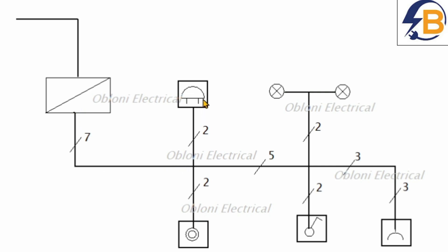Adding the two feed wires to the three socket cables, we now have five cables already. This is very important: because we are using different feeds for the bell and the switch, these two circuits must be on their own — a separate circuit for the bell and a separate circuit for the light. If we have a separate feed, there must be a separate neutral to the bell and a separate neutral to the light. Two neutral wires added to the five gives us seven wires total.